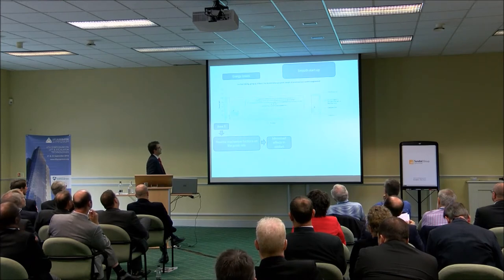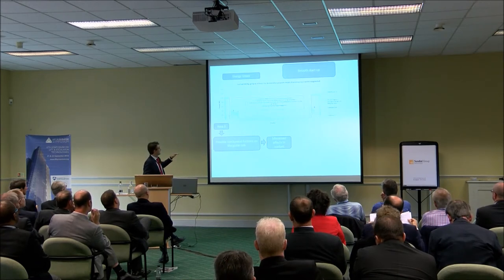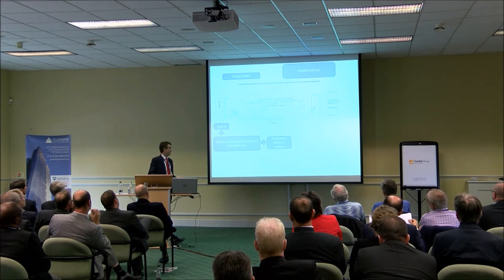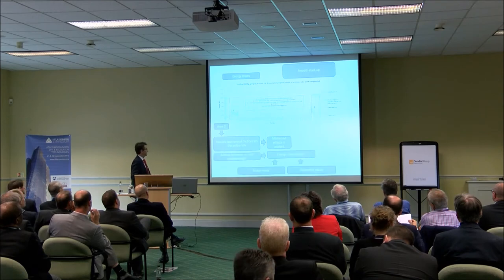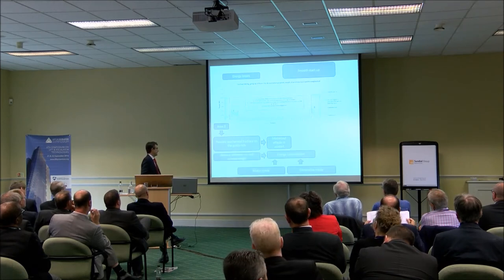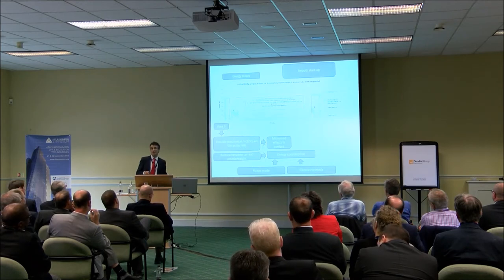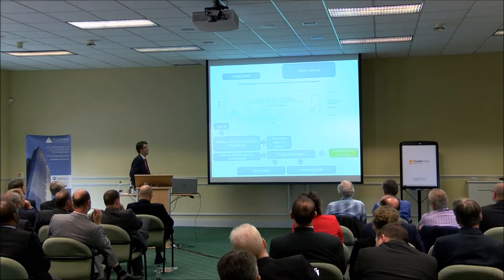Let's look at the next phase of the journey: the smooth start-up, area number 3. The lift is already in motion, working on very low frequencies because we can find mechanical frictions. We need to minimize these effects on comfort, so we need to move the car very smoothly during a period of time. We will always find energy consumption here — it doesn't matter if the motor works as a generator or as a motor. So we suggest to adjust this time properly.